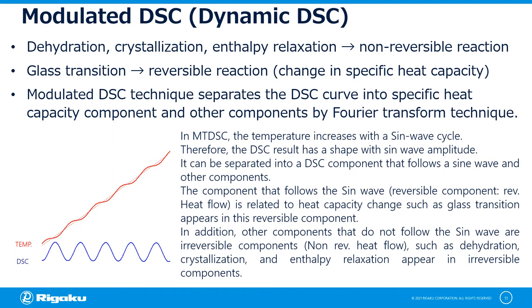In a modulated DSC, the temperature increases with a sine wave cycle. Therefore, the DSC curve has a shape with a sine wave-like amplitude and separates into a component that follows a sine wave and other components. The component that follows the sine wave will be the component related to the heat capacity, called the reversible component. Reversible heat flow and glass transition appear in this reversible component. The component that does not follow the sine wave is called the irreversible component or non-reversing heat flow. Reactions such as dehydration, crystallization, and enthalpy relaxation appear here.